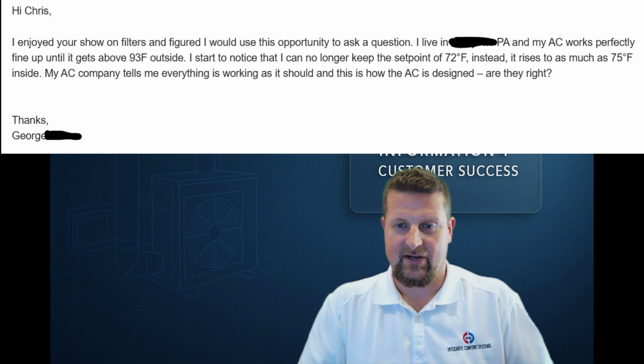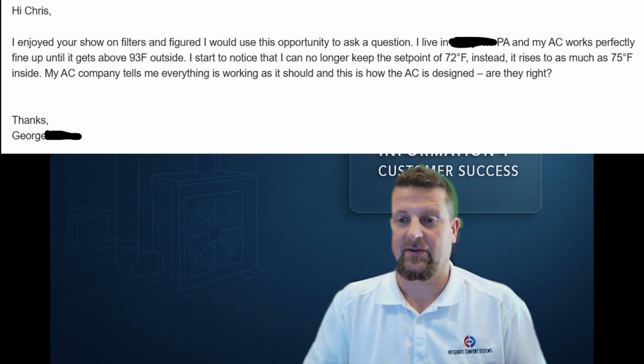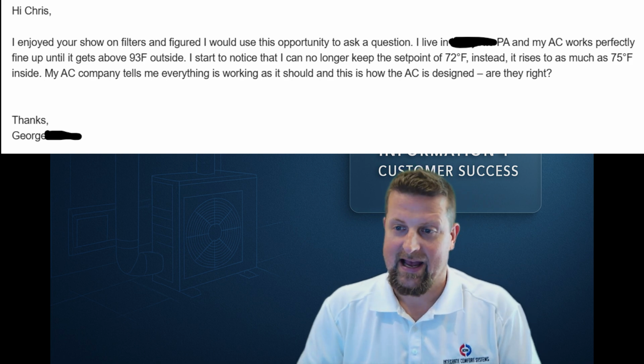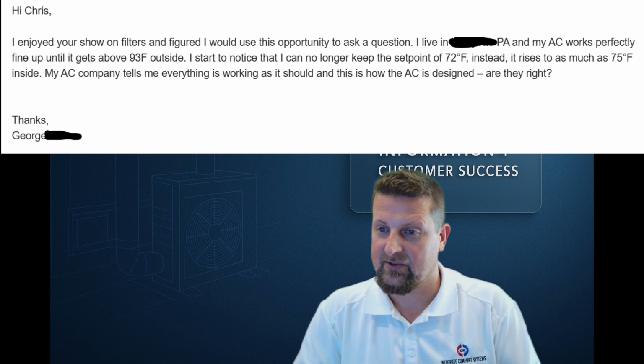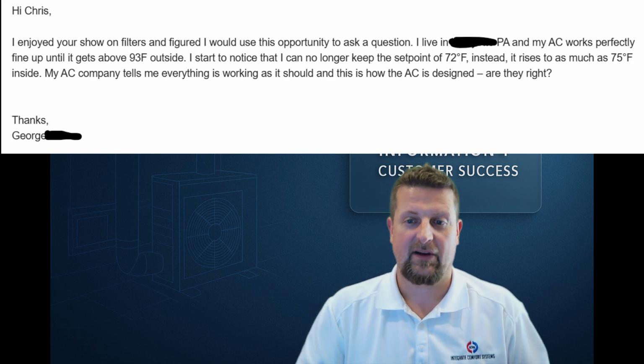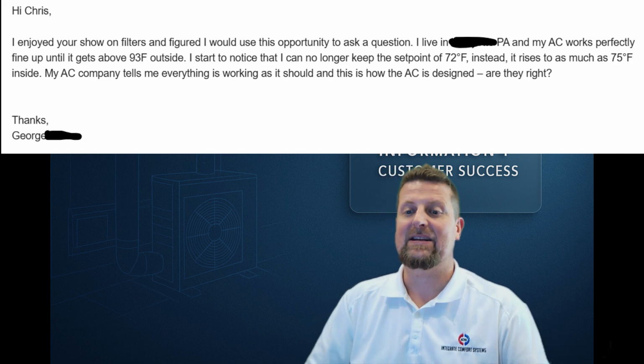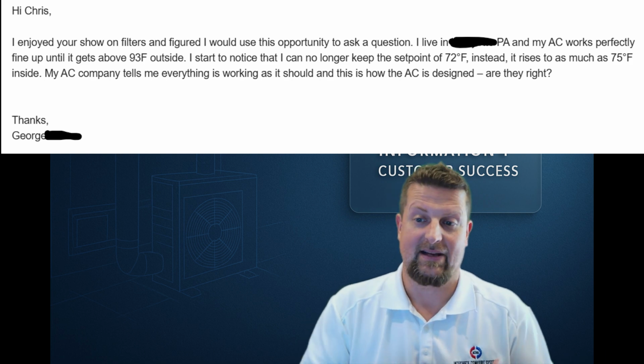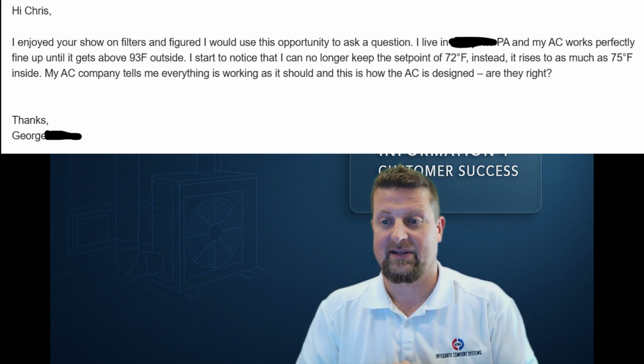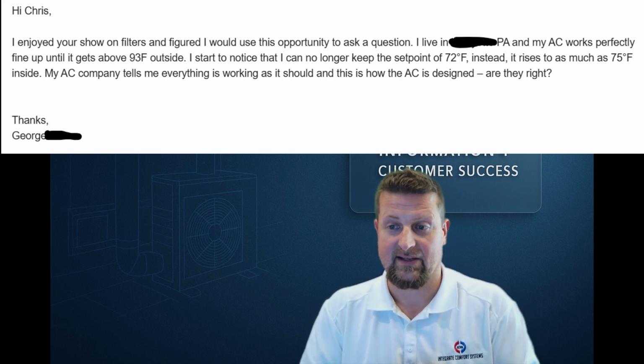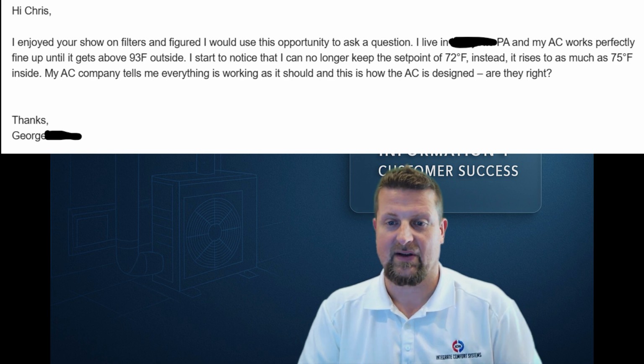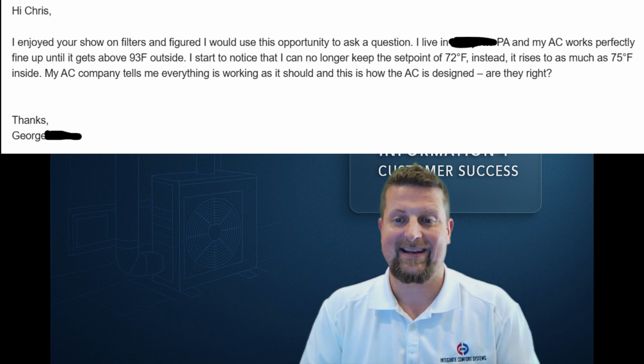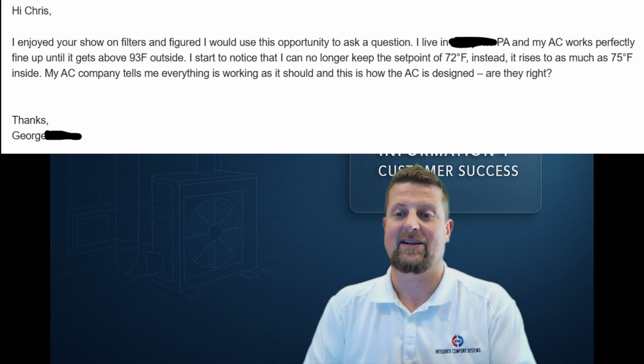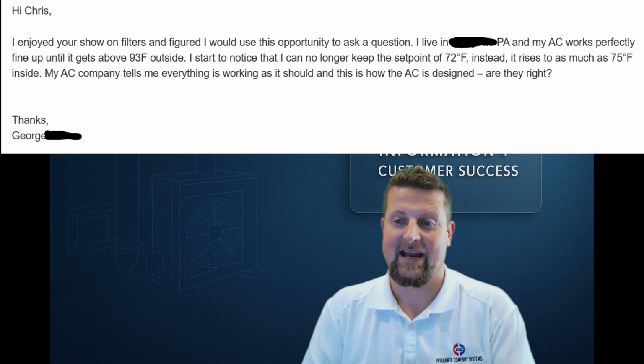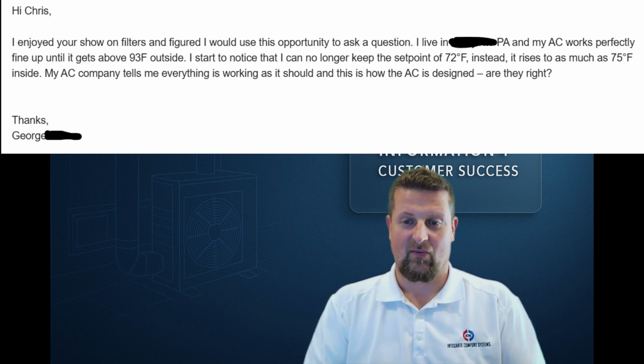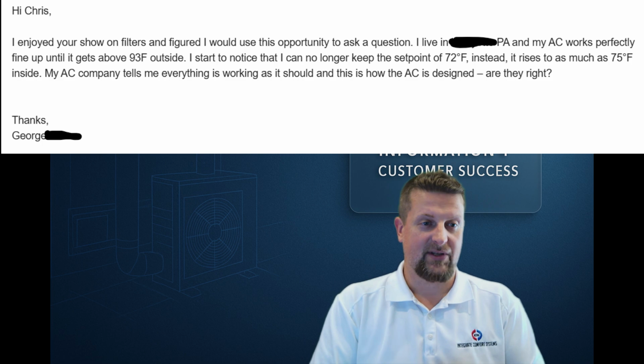Here's what George writes. I enjoyed your show on filters and figured I would use this opportunity to ask questions. I live somewhere in Pennsylvania. I don't want to expose George too much, and my AC works perfectly fine up until it hits about 93 degrees outside or above. I start to notice that I can no longer keep the set point at 72 degrees inside. Instead, it rises to as much as 75 degrees inside. My AC company tells me everything is working as it should, and this is how the AC is designed. Are they right? George, 100% they are right.